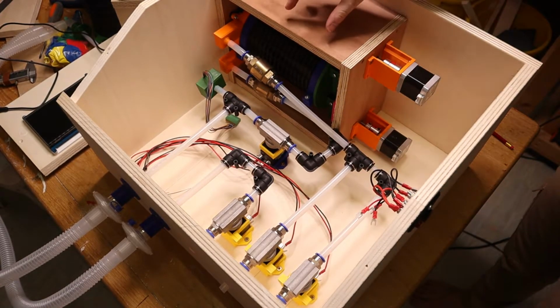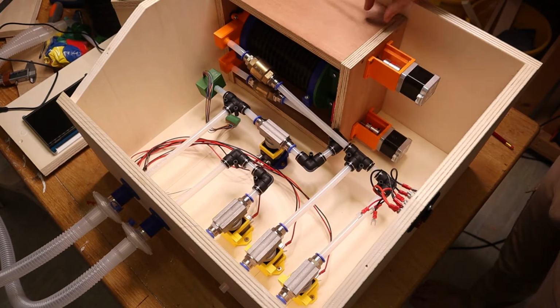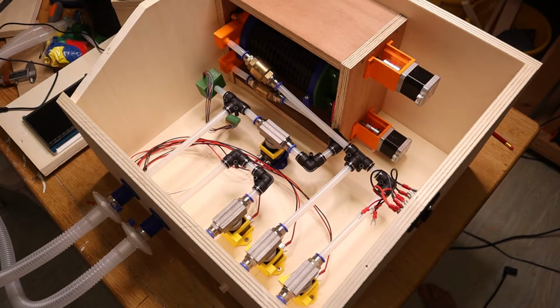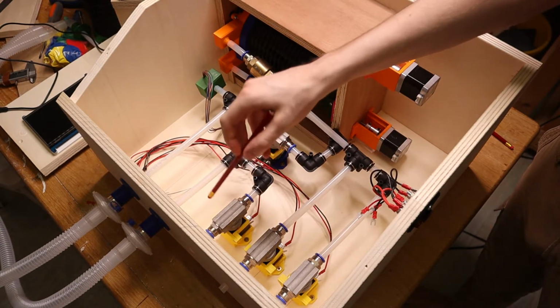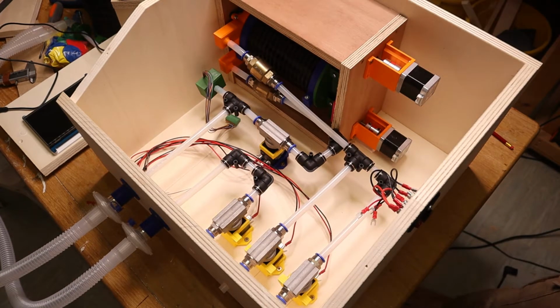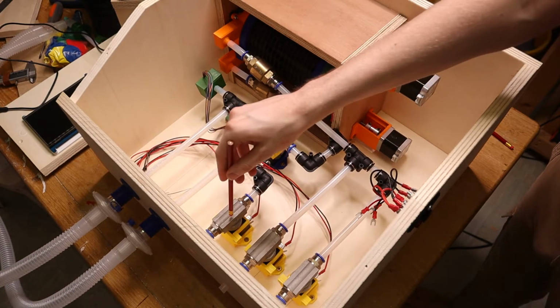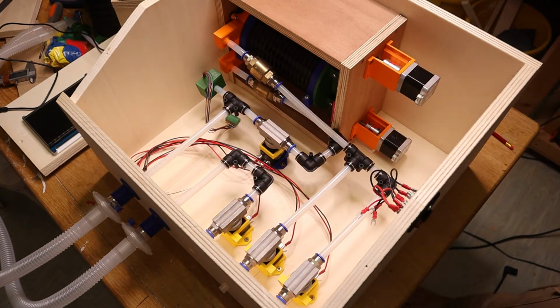And then by changing the distance with the oxygen valve open versus the distance with the air valve open, you can precisely control the concentration of oxygen that you deliver to the patient's lungs. The exhaust valve is initially open so that the patient can start to exhale. And then at the right time you have to close the PEEP valve or the exhaust valve again to maintain the correct level of PEEP, the correct level of pressure inside the patient's lungs. There must also always be an amount of positive pressure inside the patient's lungs, and you can achieve that by closing this valve at the correct time. So that is essentially how a cycle is supposed to work.